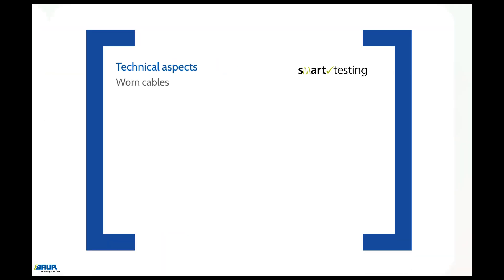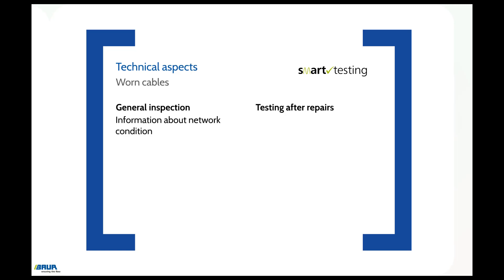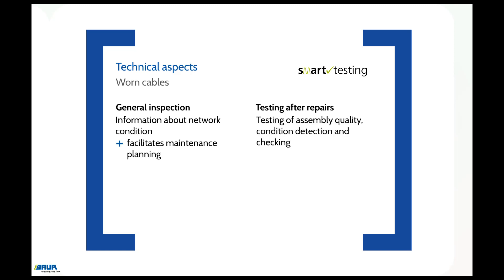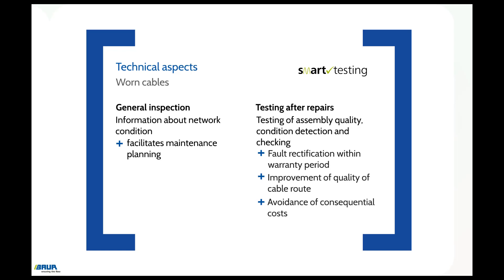During cable testing on worn cables, a distinction is made between a general condition evaluation of critical cables and the inspection of cables after repairs. The general inspection supplies information about the condition of the network status, which facilitates maintenance planning. Testing after repairs has two purposes: firstly, to check the assembly quality, and secondly, for condition detection and to check whether the problem has been rectified. This allows claims to be asserted during the warranty period, the quality of the cable route to be improved, and consequential costs to be avoided.